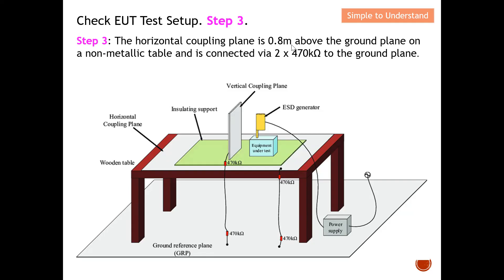Step number three: the horizontal coupling plate must be 0.8 meters above the ground, placed on a non-metallic table, and connected via two 470 kilo-ohm bleeding resistors to the ground plane. As shown, the wooden table needs to be 0.8 meters tall. The two bleeding resistors connect the horizontal coupling plane to the ground reference plane.